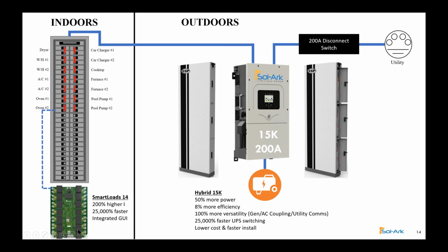What the SmartLoad does is replace the need for an essential loads panel or critical loads panel. It just throws that concept in the trash. If you can bring 14 circuits out of your main distribution panel and have real-time dynamic control over them with the SmartLoads panel, you don't need a critical loads panel.